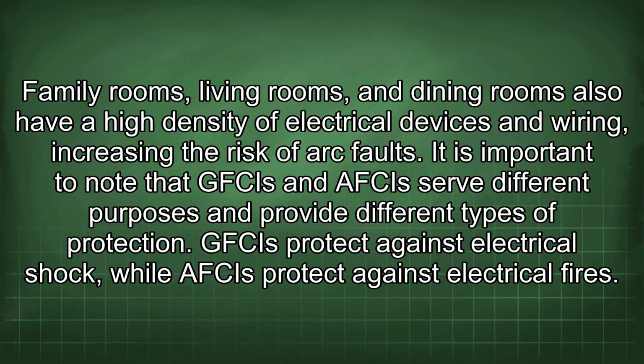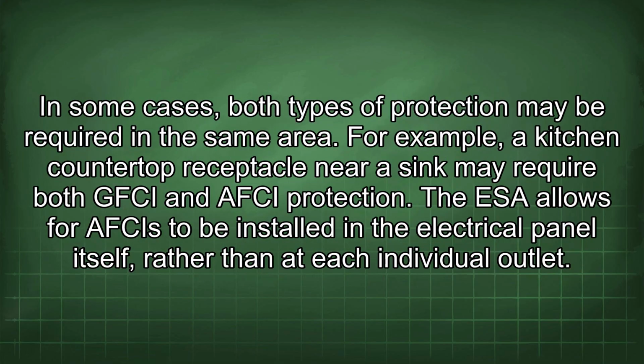of arc faults. It is important to note that GFCIs and AFCIs serve different purposes and provide different types of protection. GFCIs protect against electrical shock, while AFCIs protect against electrical fires. In some cases, both types of protection may be required in the same area. For example, a kitchen countertop receptacle near a sink may require both GFCI and AFCI protection.